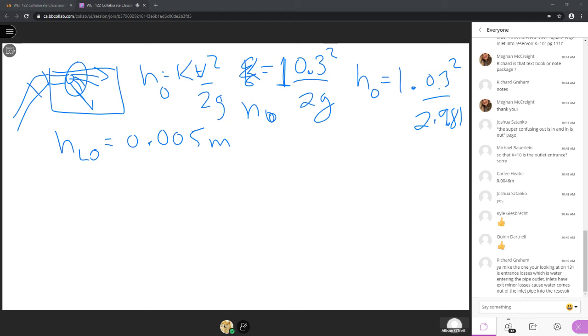So if we look at the suction side of the line, it has a square-edged outlet. So that means the water is leaving the reservoir, and it has two long radius 90-degree elbows. Now, you'll notice that on this side, we haven't done the head losses in this pipe yet. It's a different diameter and it will have a different velocity. Okay, so we will have to treat this as its own separate pipe.